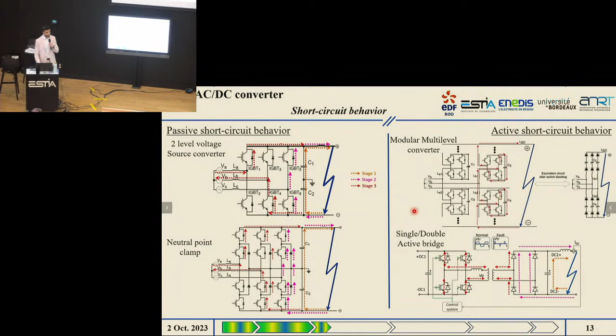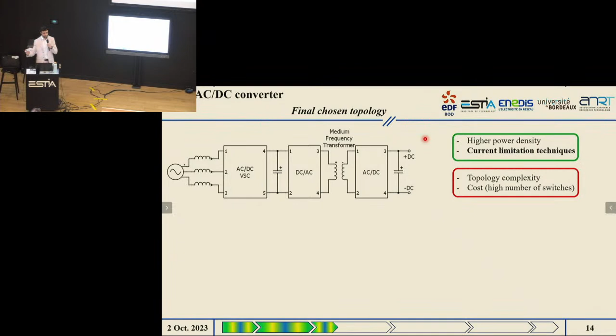For these reasons, we chose to exploit a topology that corresponds to an isolated converter, mainly due to two main characteristics: the possibility of reaching high power density, mainly because of the use of a medium or high frequency transformer—in our case a medium frequency transformer, significantly small in volume and mass—and the second, most important characteristic, the ability to limit short circuit currents, which could help us coordinate operation with other protection devices placed downstream in cascade.